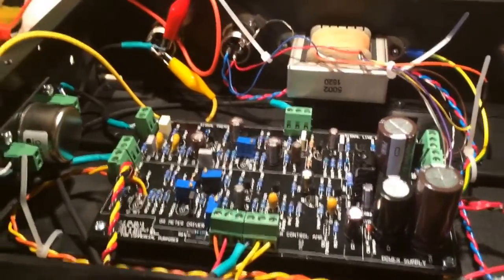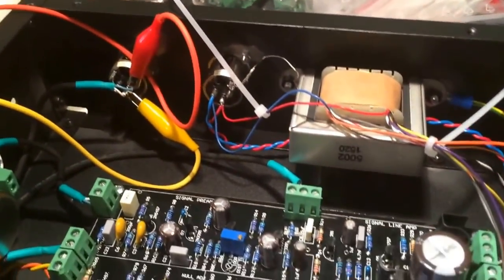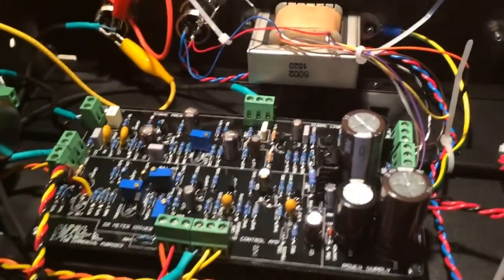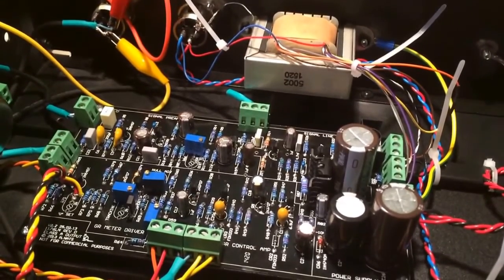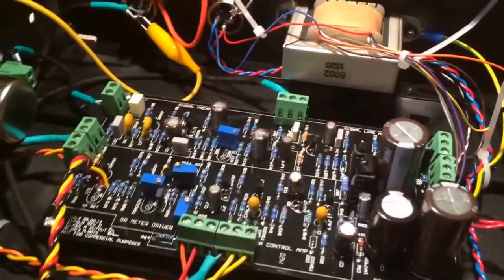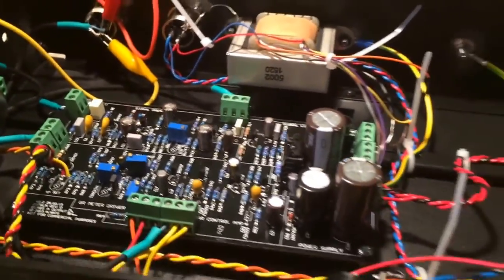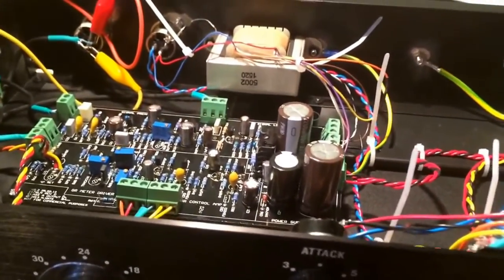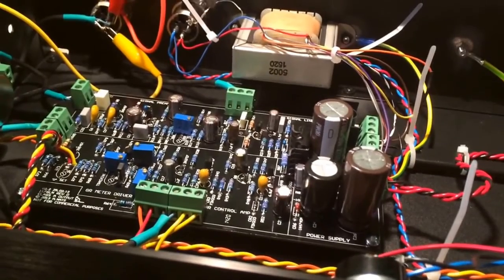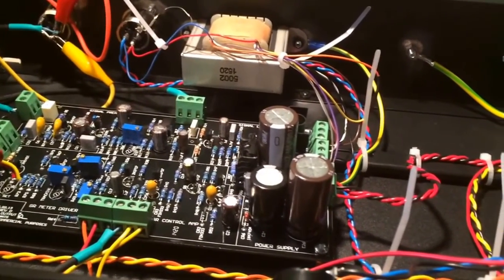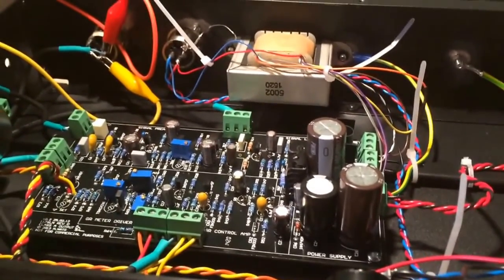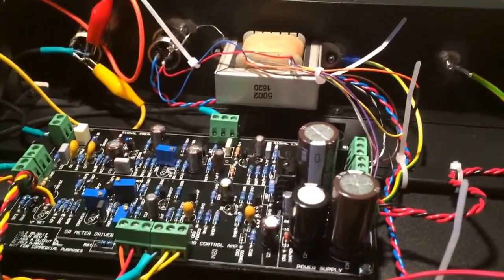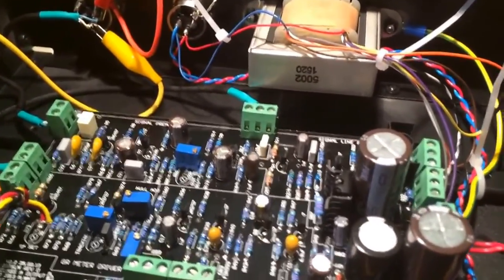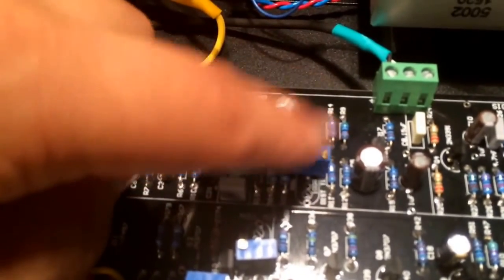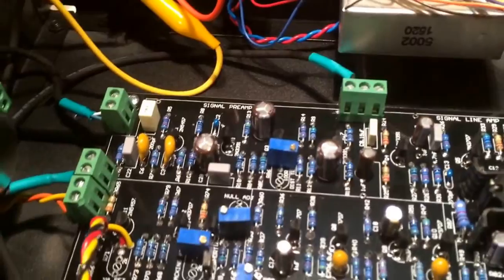Okay. The idea of how to perform the test is you input a 500 hertz signal at a certain level, which is 24 millivolts. If I'm not mistaken, it's around minus 30 dB. You also put the output around 0 dBs, and you do a real-time analysis on the frequency response, and you find out what the current total harmonic distortion is. Then you fine-tune this trim pot until you reach the minimum distortion. Okay.